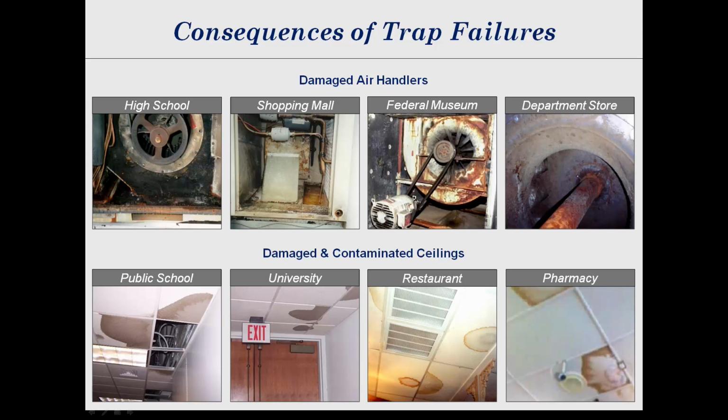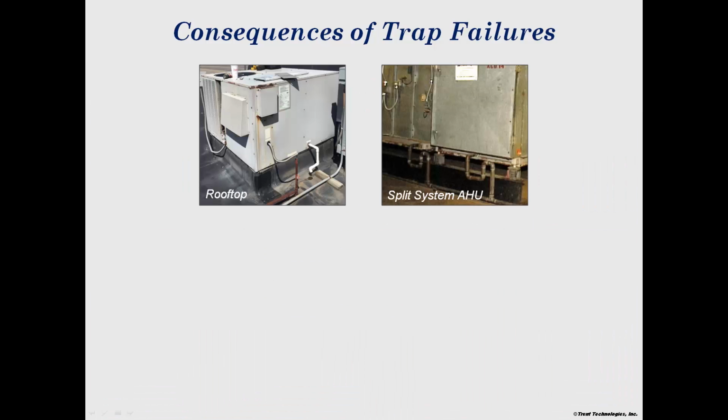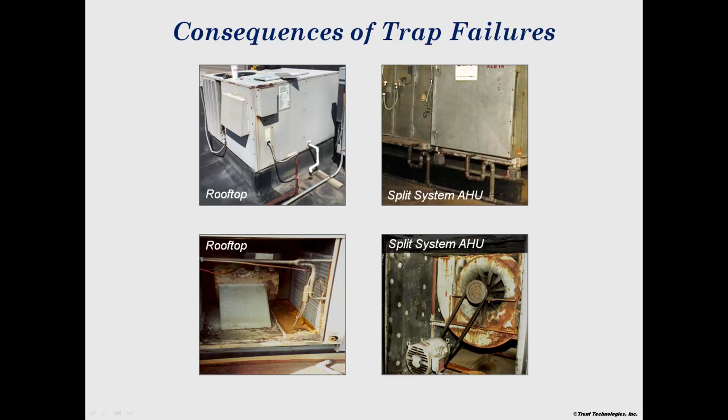The wetted surfaces cause corrosion and provide a fertile growth place for contaminating organisms that result in costly property damage and significant health threats. The cause of these conditions is not readily visible to the building owner or manager, so the need to address the situation may not be apparent. Typically what they see during operation are units like the one shown in these photographs. Only when the cabinet is open can the damage be revealed, as shown in these photographs.